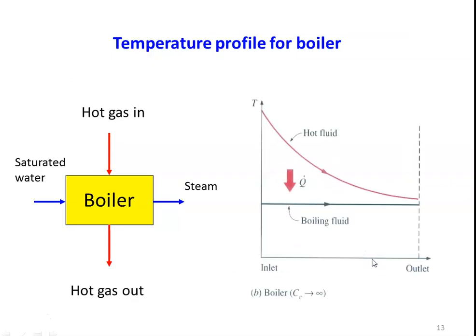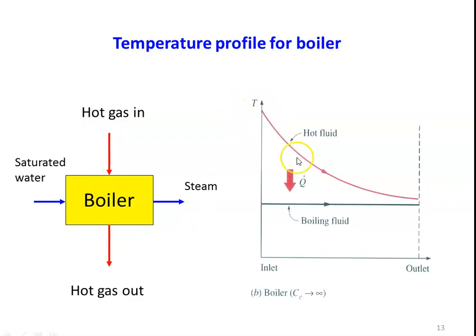This is the temperature profile of a boiler or evaporator. In the evaporator, saturated water enters, is heated up, and steam leaves on the other side. For the conversion of water into steam, the fluid temperature remains constant during the phase change process — the boiling fluid temperature is constant. The hot gases enter with higher temperature and decrease in temperature, transferring that heat to water which is converted into steam. The heat given to the fluid increases the latent heat of evaporation.